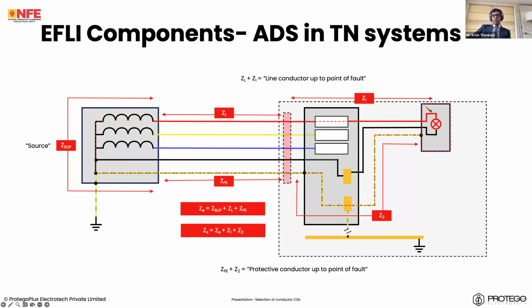Our idea is that if a fault occurs here, the impedance of this loop, the earth fault loop, so I call it earth fault loop impedance, has to be low enough such that the amount of current that will flow will cause the device to disconnect in the required time. That time is given in the standard. It is 0.4 seconds for final circuits in a TN system, 0.2 seconds for final circuits in a TT system, 1 second for distribution circuits and certain final circuits in a TT, and 5 seconds for distribution circuits and certain final circuits in a TN. Don't focus on the time right now. The idea is loop impedance.